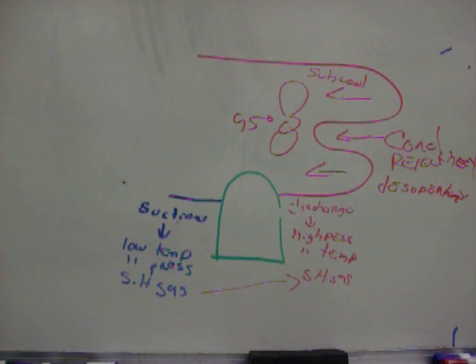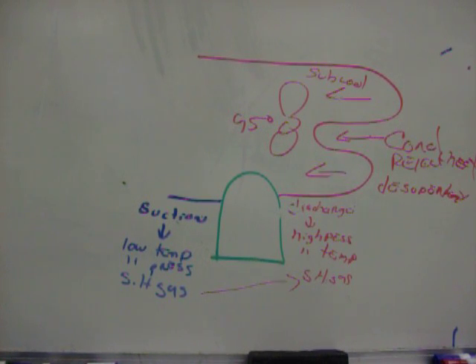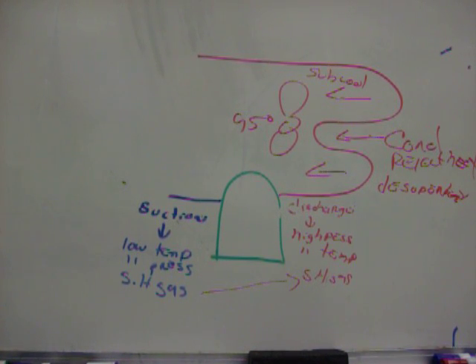De-superheating at atmospheric pressure would be removing any heat from steam above 212 degrees. Water boils at 212. So you pull all the heat down, and at 212 you start to condense. And if you pull the temperature from that water down from 212 to 202, then you did 10 degrees of sub-cooling.